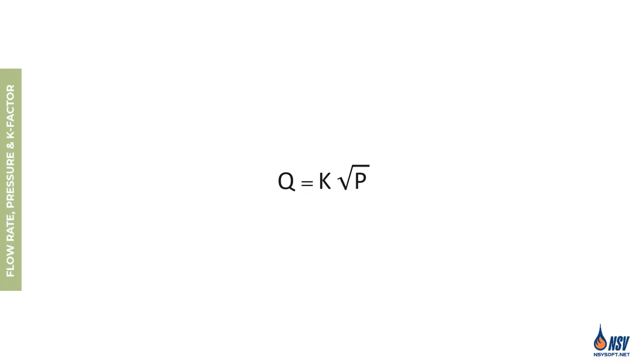The equation Q = K√P is one of the most widely used formulas in hydraulic calculations for fire sprinkler systems. We apply it when we know the K factor and pressure to determine the flow rate, or when we know the K factor and flow rate to calculate the required pressure. It's also useful for simplifying system calculations by determining an equivalent K factor for a section of the sprinkler system. In the following sections we'll explore how to apply the equation to calculate flow rate, pressure, and the equivalent K factor.